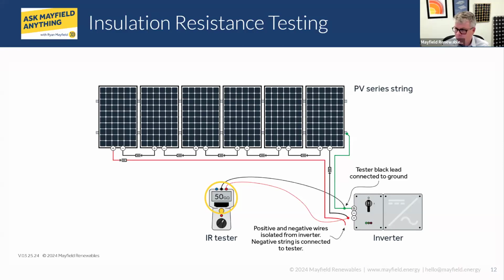Yeah. The only thing I would add is, for folks out there on the front line of troubleshooting PV systems, anytime you come across a string inverter that has an arc or ground fault detected, an insulation resistance test is nine times out of ten required in order to determine the root cause, identify if the issue is still active, and ultimately where that issue is. There are many, many nuances to the architecture of the system and what components you have in there to effectively deploy it. But if a service provider is not using a Megger tool to address an inverter fault, an arc fault or ground fault, then they're not really exhausting all the tools and options to be able to identify that issue.